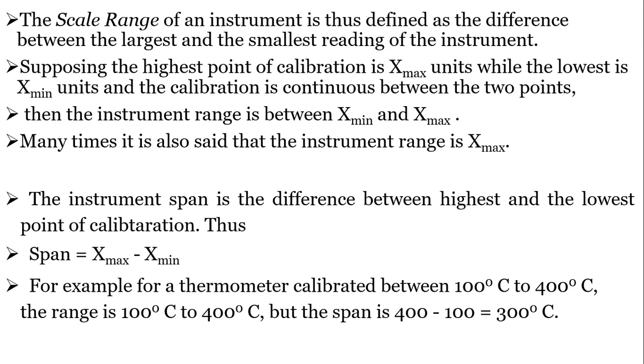Span is the algebraic difference between the highest and the lowest point of calibration — that is, x-maximum minus x-minimum. For example, for a thermometer calibrated between 100°C and 400°C, the range is 100°C to 400°C, but the span is 400 minus 100, which is 300°C. If the range is −100°C to 400°C, the span is 400 minus (−100), giving 500°C.